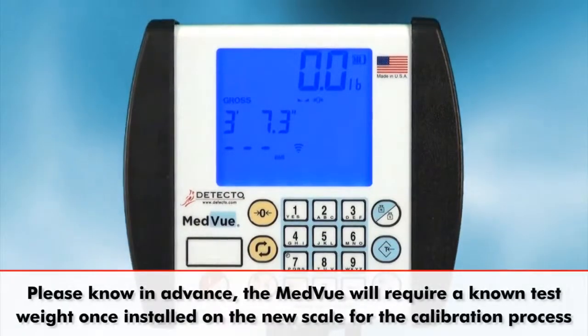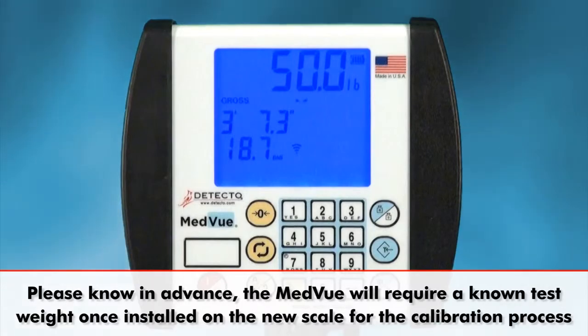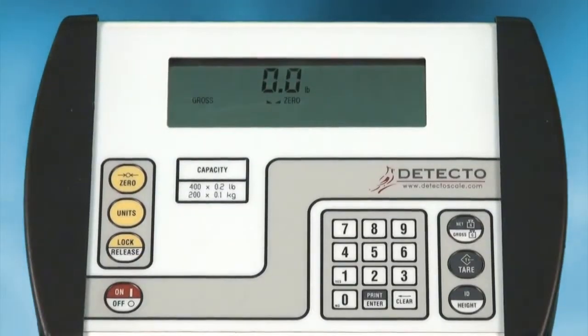Please know in advance the MedVue will require a known test weight once it's installed on the new scale for the calibration process.